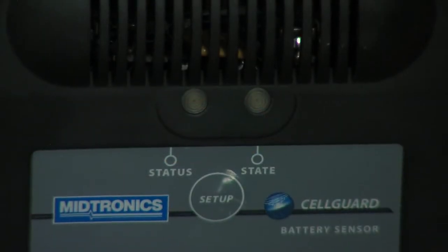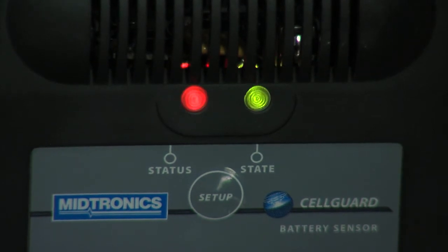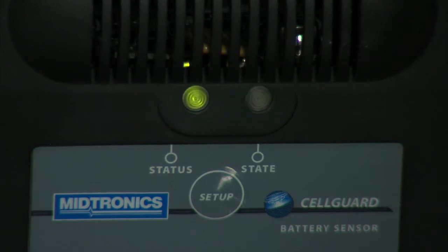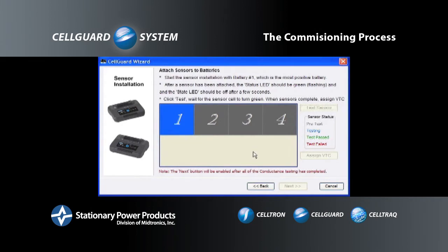The LEDs on the sensor will go through their power-up sequence of red, red, yellow, yellow, green, green. Wait until the status LED is in a continuous flashing green state. Now click Test Sensor. The square for sensor 1 will turn blue, indicating the commissioning of that sensor has started. It is important to connect only one sensor at a time to avoid getting an error message. When the first sensor is commissioned, the square will turn from blue to green, and you can connect the next sensor.